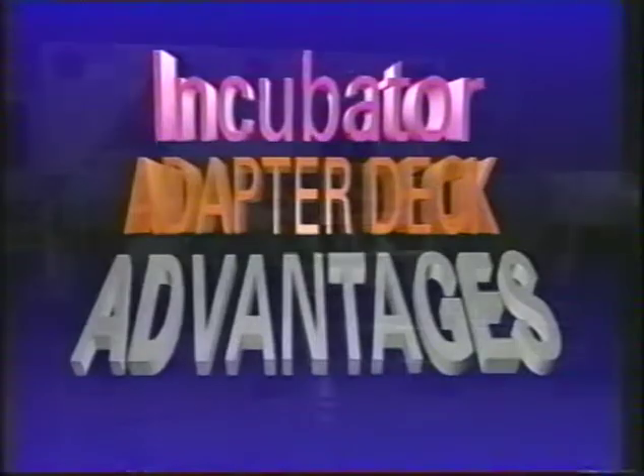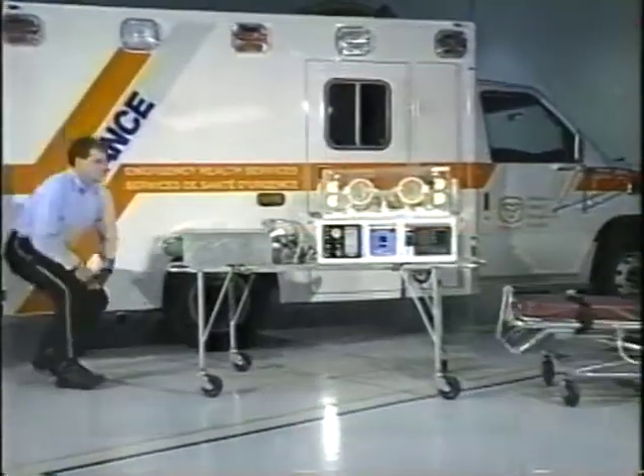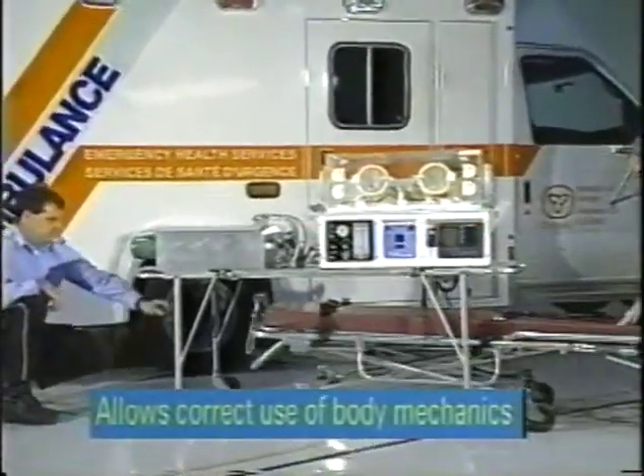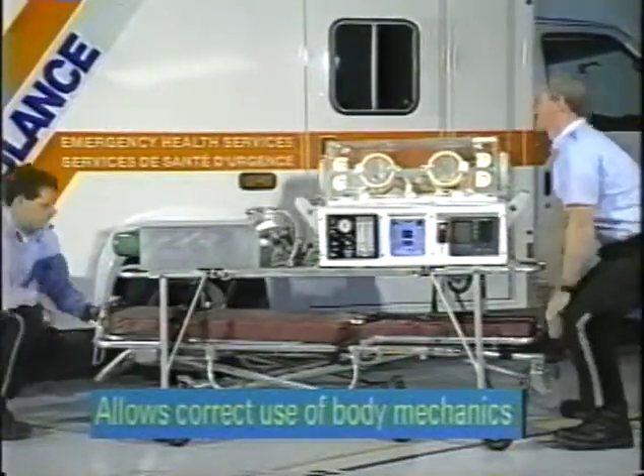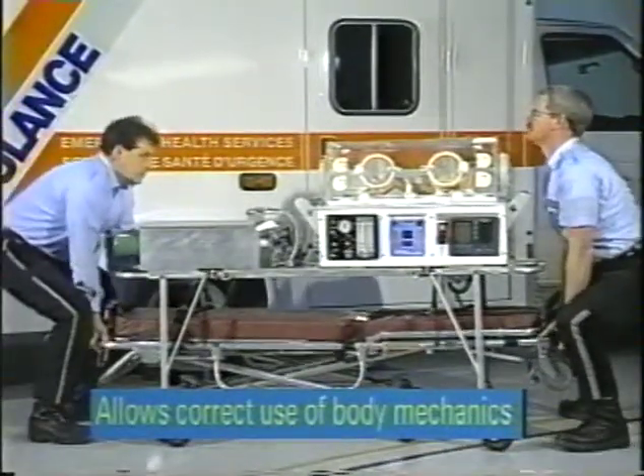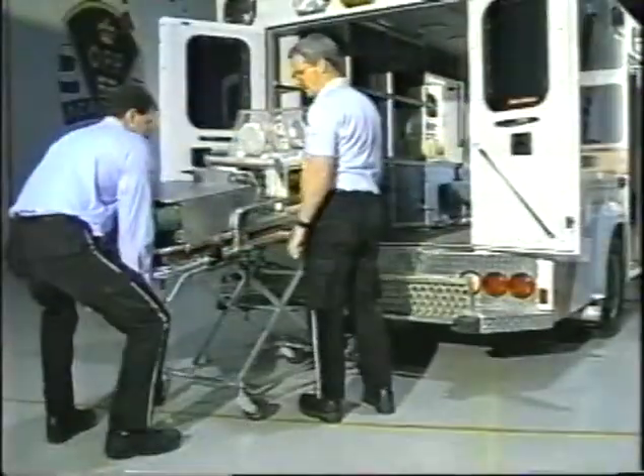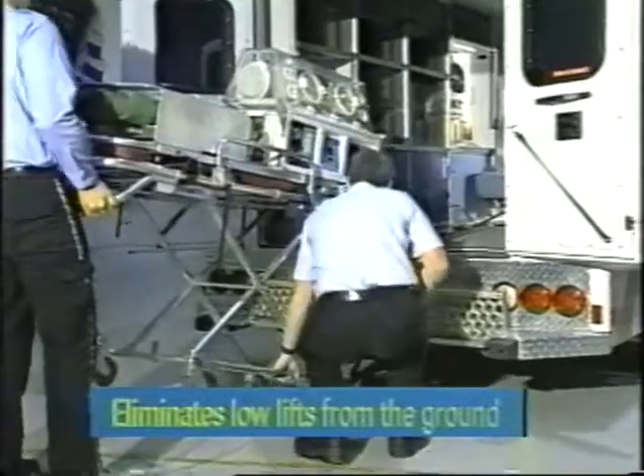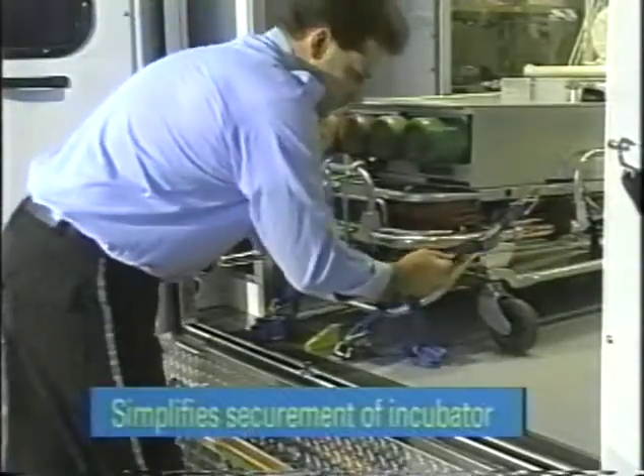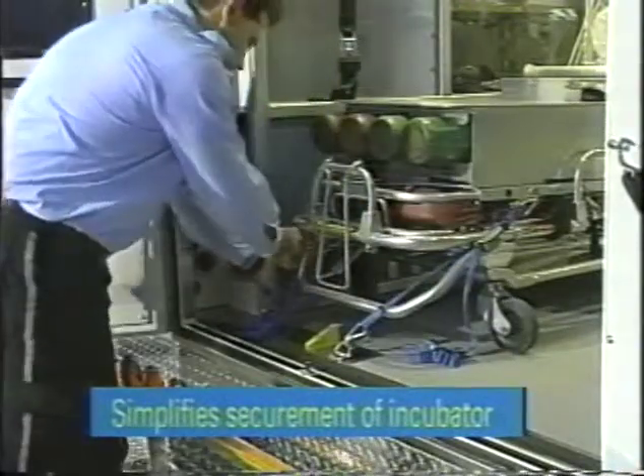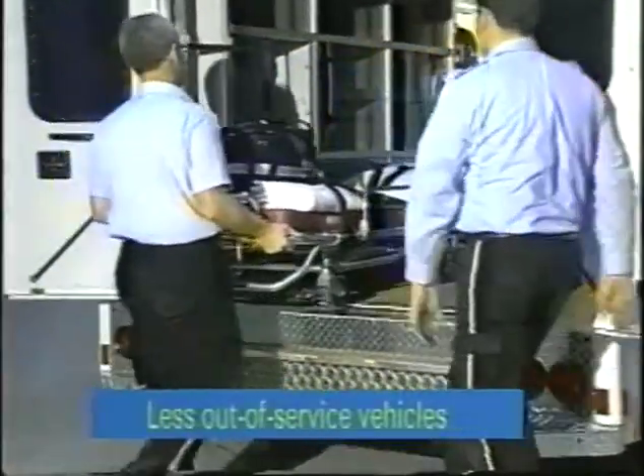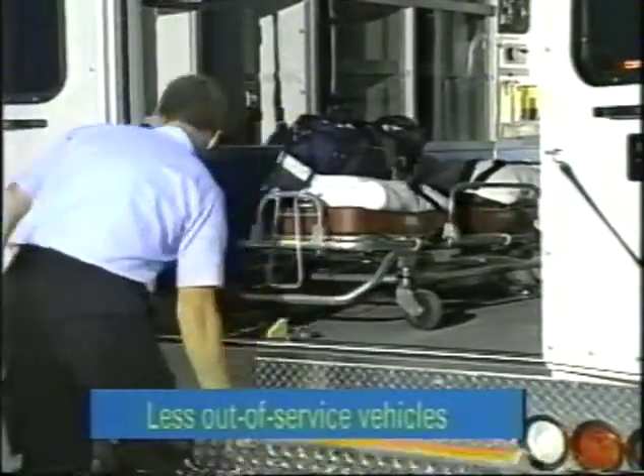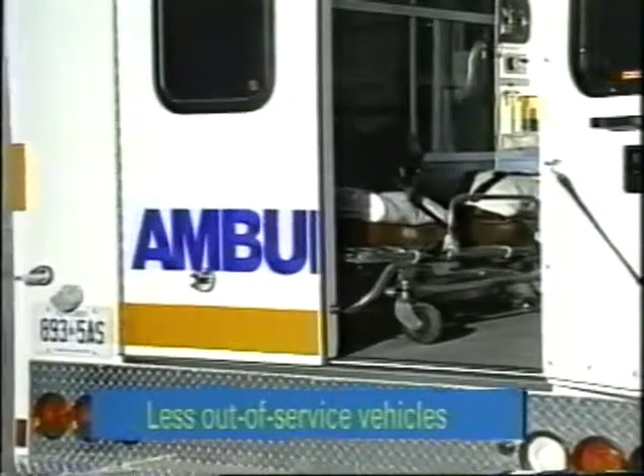There are many advantages provided by the new incubator adapter deck. It allows the use of correct body mechanics during transfer of the incubator to the stretcher. Ready, set, up. It eliminates low lifts from the ground when the 35A load assist stretcher is used. It simplifies the safe securement of the incubator within the ambulance or aircraft. It reduces the number of out-of-service vehicles that occur with incubator transfers because the main stretcher is not left behind.